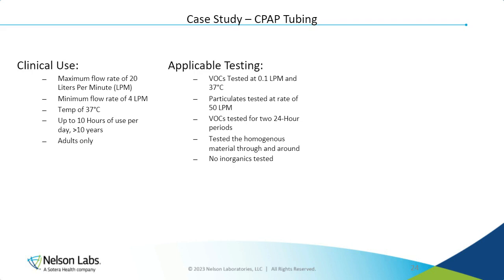Additionally, the tubing was tested by air being pushed through and around the device, meaning a greater surface area was tested. When comparing the clinical use to the applicable testing, this testing was robust and appropriate. This will yield relevant information and data to be used within a toxicological risk assessment.